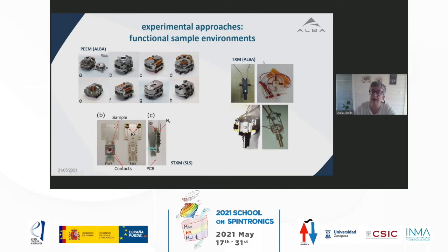On the other hand, on the right, if you see the TXM, the center has to be completely free of anything, and the sample holder has to be very flat in this direction so that I can rotate to look at the sample with different angles. And in the STXM, which is the lower left example, it is the same. The region of the sample has to be relatively flat, so I can come close with the optics, and so I can rotate at least a little bit to look at different magnetization components, so not only the normal components. So this is also something to take into account.